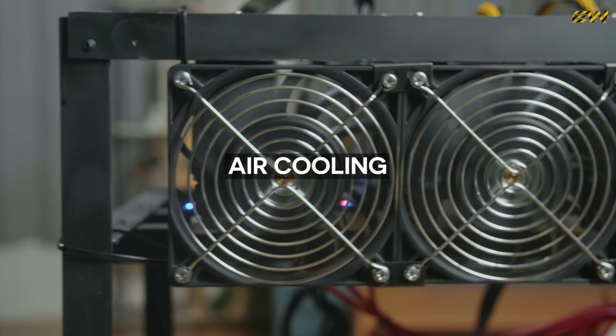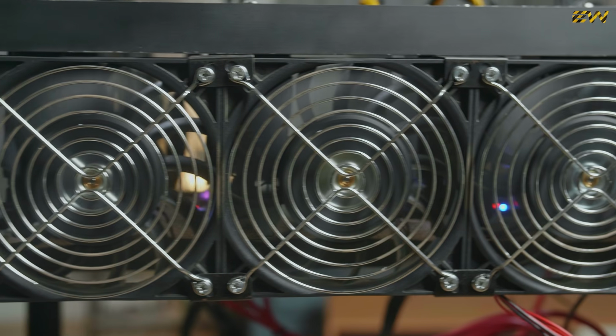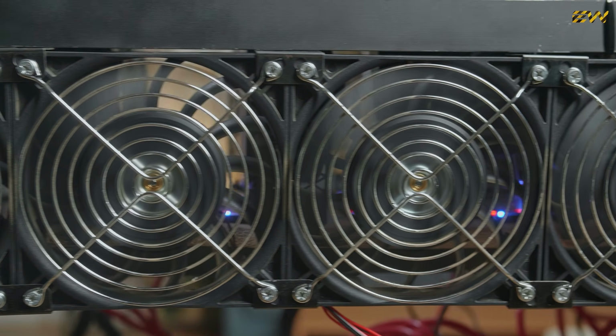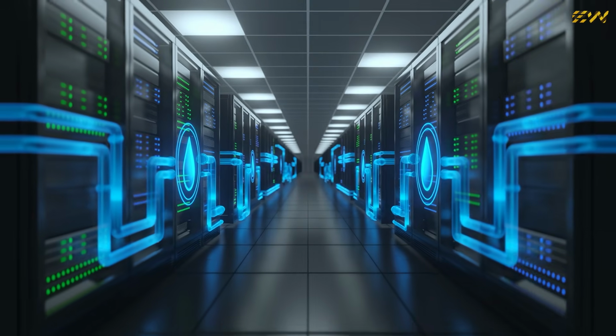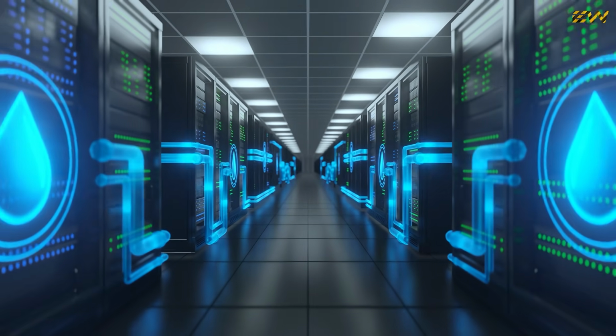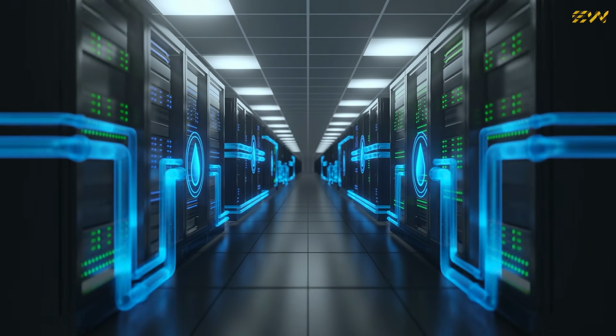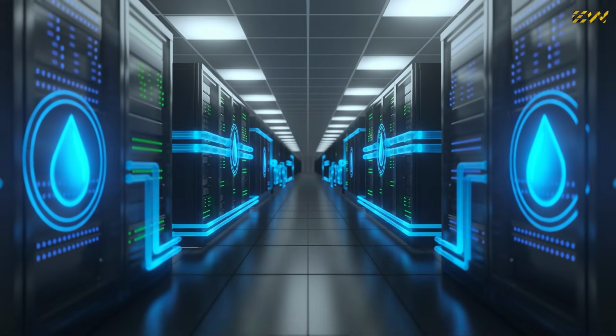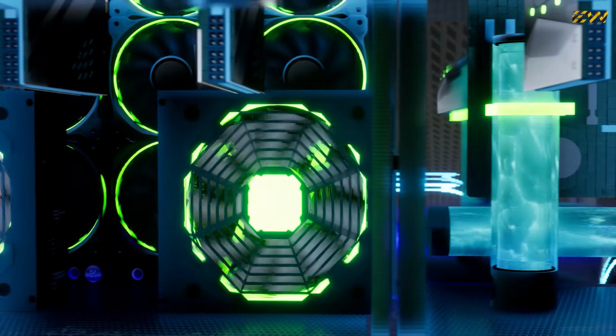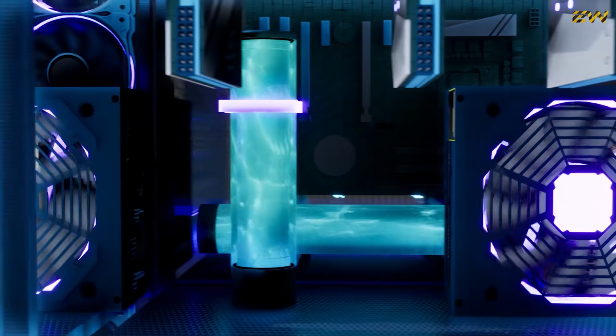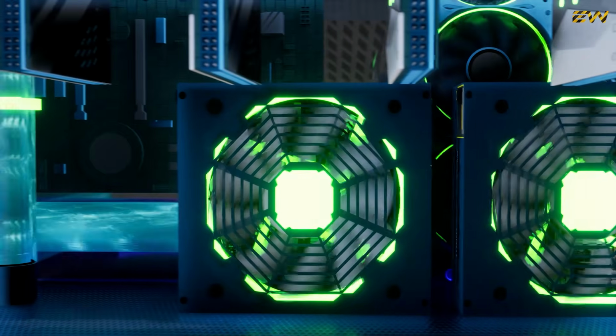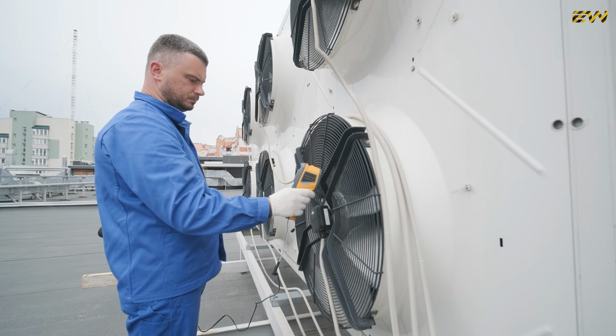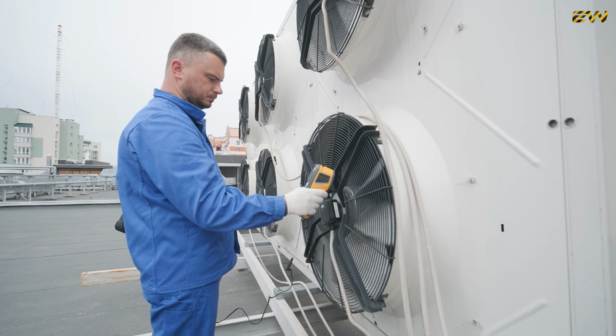Air cooling, once standard, caps out around 20 to 35 kilowatts per rack. Beyond that, liquid cooling becomes mandatory. Direct-to-chip cooling circulates coolant through cold plates attached directly to GPUs. Immersion cooling submerges entire servers in dielectric fluid. The digital revolution is now a thermal engineering challenge.